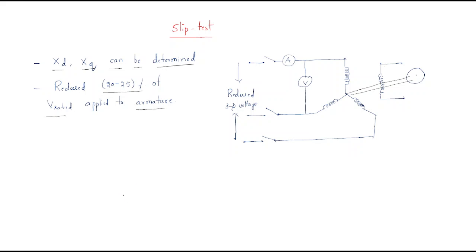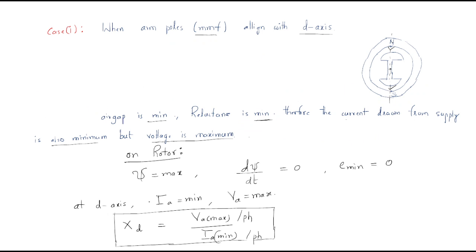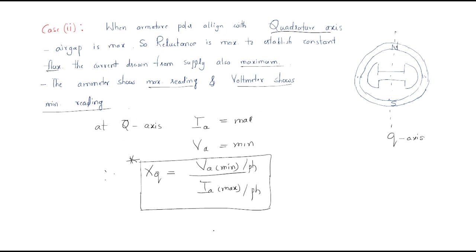In the last session we discussed the slip test, in which we find the direct axis reactance Xd, that is Vmax by Ia minimum, and the quadrature axis reactance Xq, that equals Va minimum by Ia max.